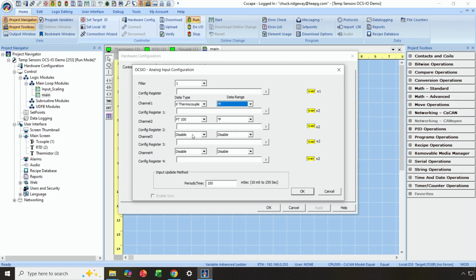Why did I do this? Well, if I do that, then the module is not expecting there to be any kind of sensors connected, and it won't throw an alarm condition if that sensor is missing, or not generating a signal, because it's obviously not missing. There's not supposed to be one there. Okay, so that's the configuration for the universal analog input module.